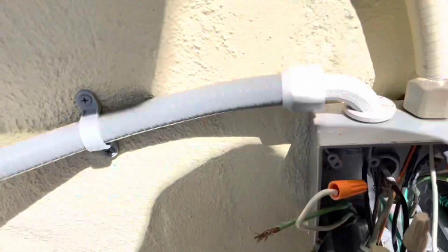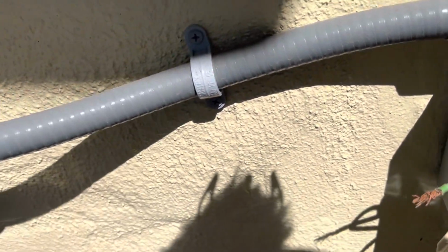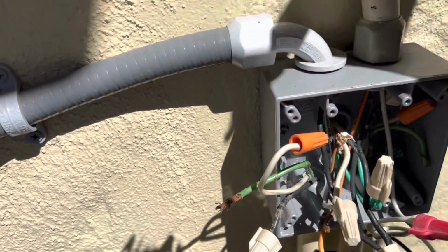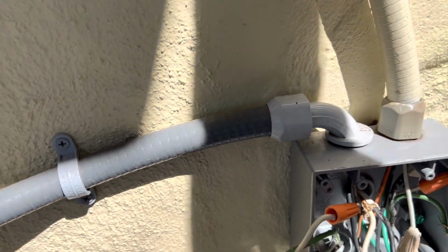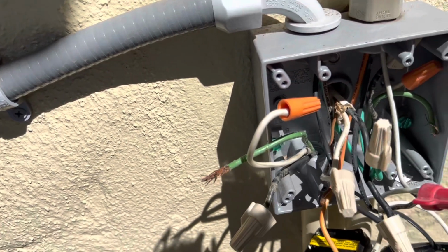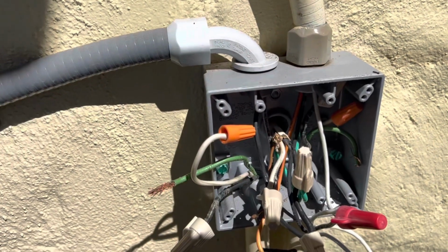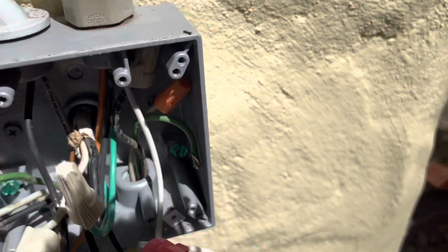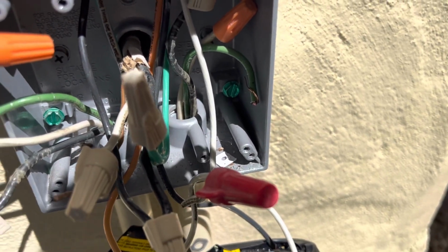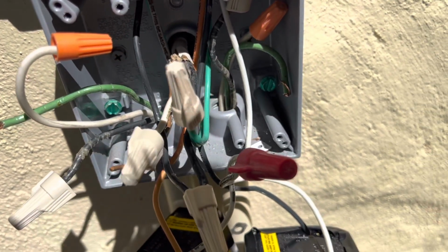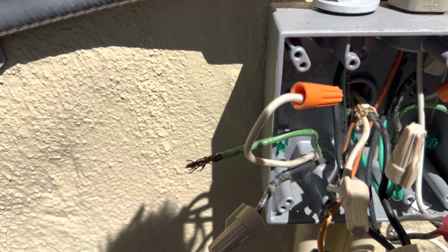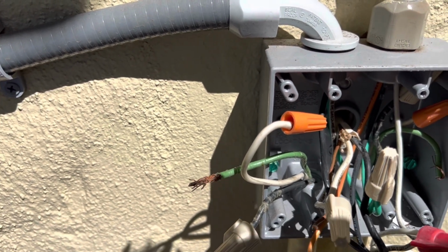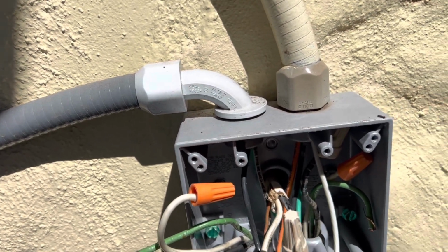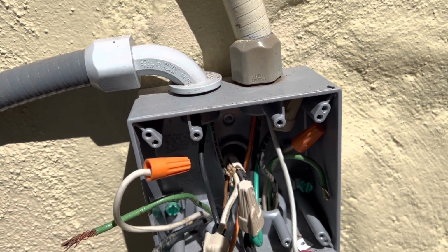Is there power anywhere else to this box? Yes, so now I've got power there, but no power to this GFI. That GFI is switched, so... Okay, so this GFI is live now, and that's attached to this timer. So we're making progress. There's a whole bunch of grounds here that are just not attached to anything, and that might be part of the problem. It's sensing a ground fault, so we should cap all these grounds off or tie them all together, but we need to find where the power for this transformer is coming from.